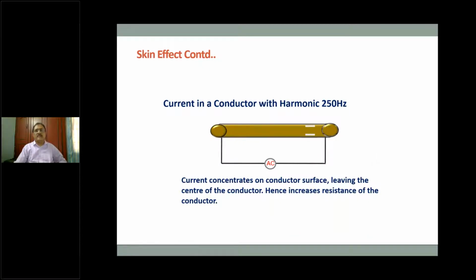So if you go to an industry, you might find that some sheath or cover provided on top of the bus bar has melted and flowed. That's a sure indication of harmonics flowing in the bus duct. Similarly, the bus ducts will get loosened at the joints, and that will create vibration and therefore a huge humming noise. These are indications of harmonics.